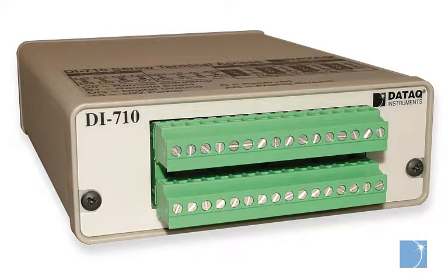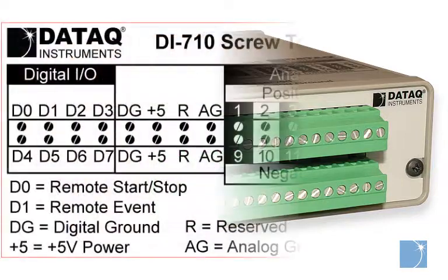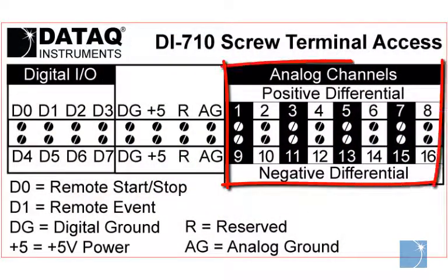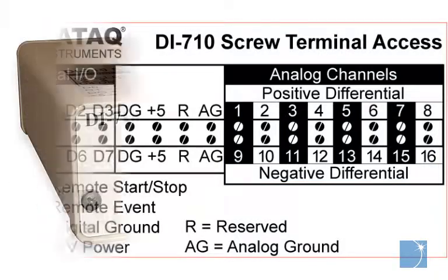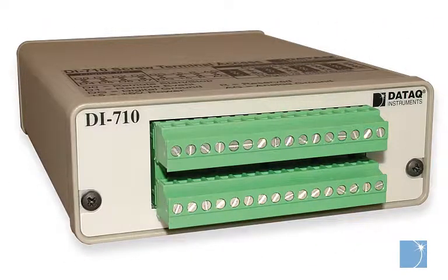The DI710 is a portable USB or Ethernet connected data acquisition system featuring 16 analog channels that can be configured for single-ended or differential operation. DI710 series instruments have a full-scale measurement range from ±10 mV to ±10 V across four programmable measurement ranges with 14-bit resolution.